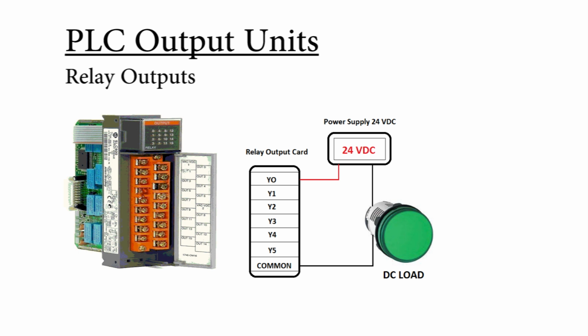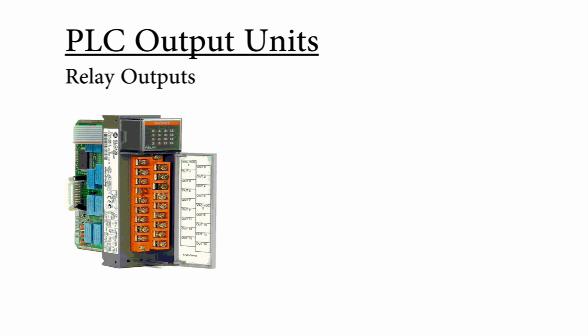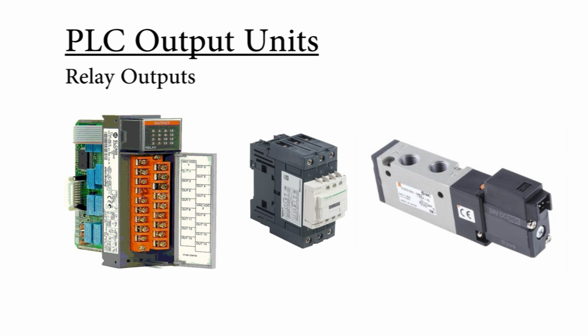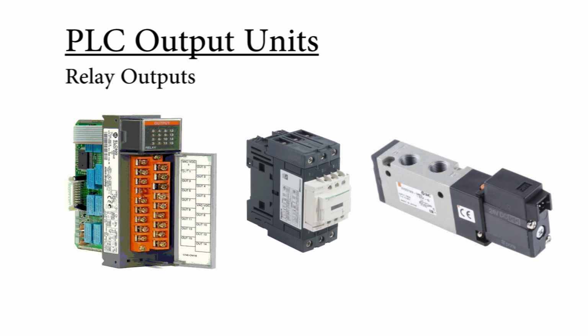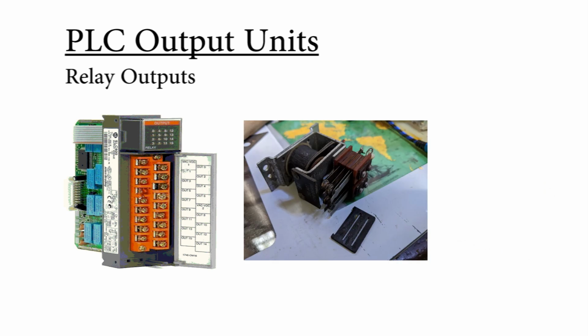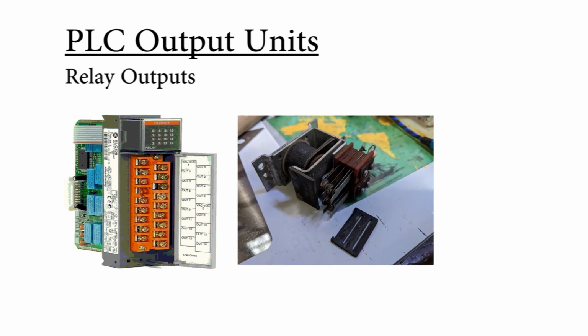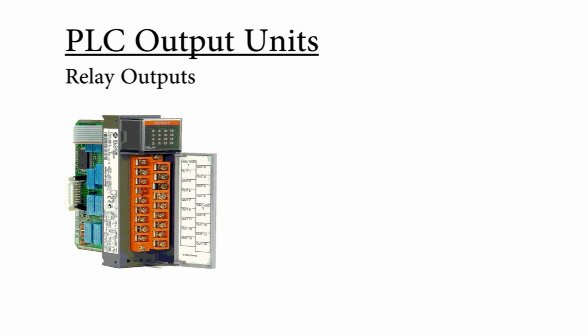A relay takes some time to close its contacts, so this means that relay output cards are not suitable for high speed switching applications. Relay output cards are suitable to turn on small solenoid valves and contactors, but with larger loads and frequent switching, relay contacts can get damaged or short circuit easily.